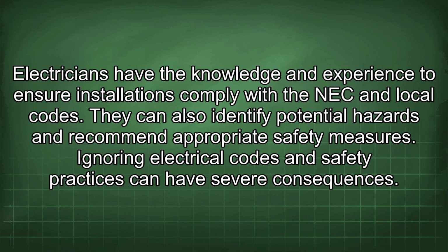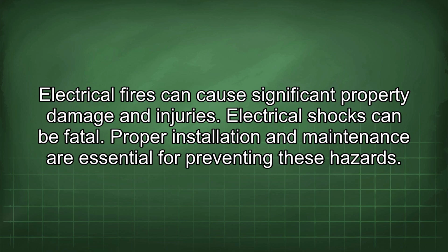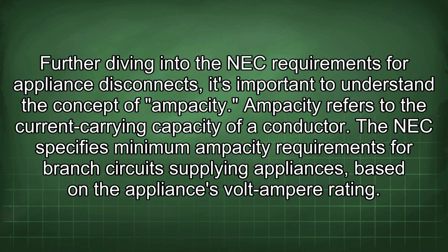Ignoring electrical codes and safety practices can have severe consequences. Electrical fires can cause significant property damage and injuries. Electrical shocks can be fatal. Proper installation and maintenance are essential for preventing these hazards. Further diving into the NEC requirements for appliance disconnects, it's important to understand the concept of ampacity. Ampacity refers to the current carrying capacity of a conductor. The NEC specifies minimum ampacity requirements for branch circuits supplying appliances, based on the appliance's volt-ampere rating.